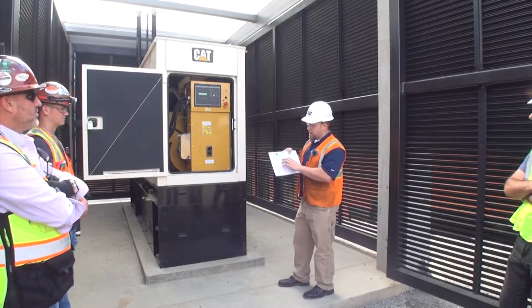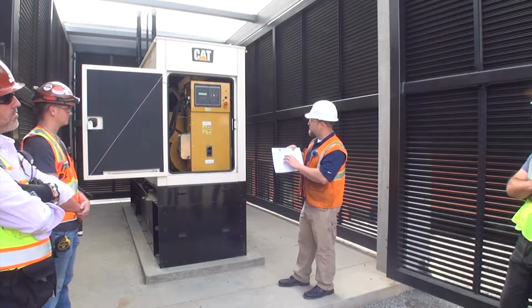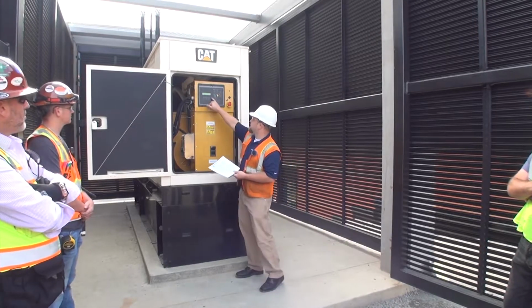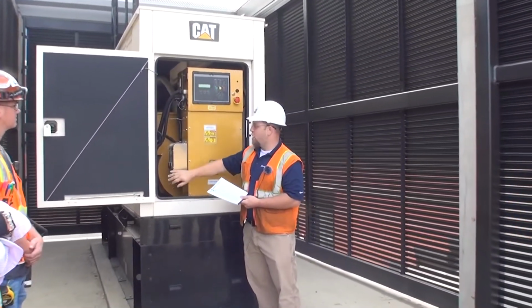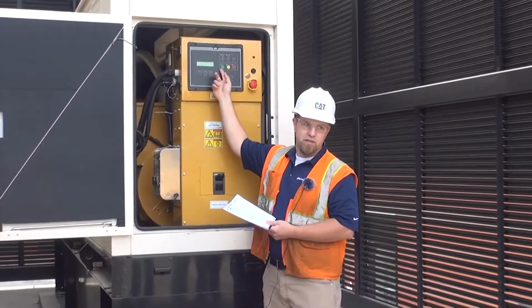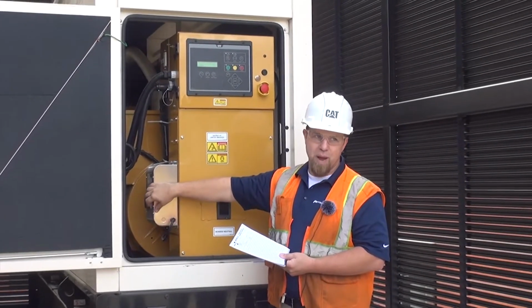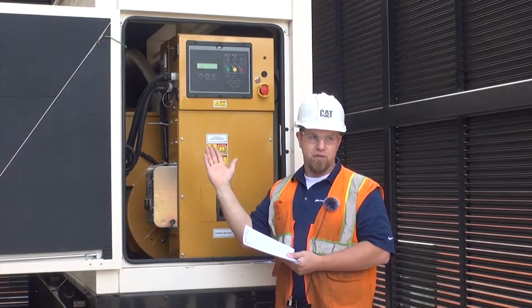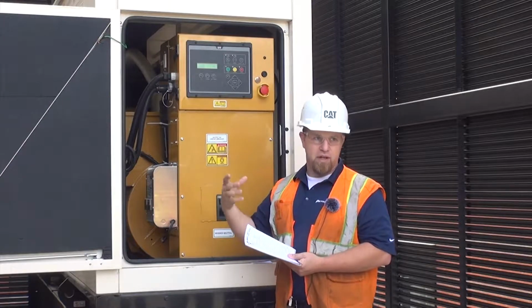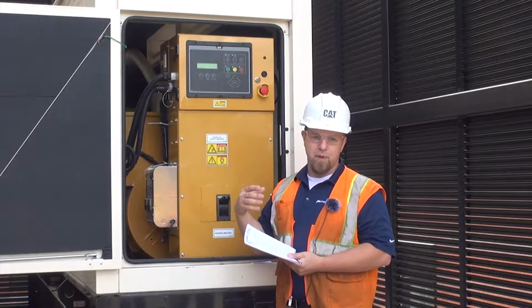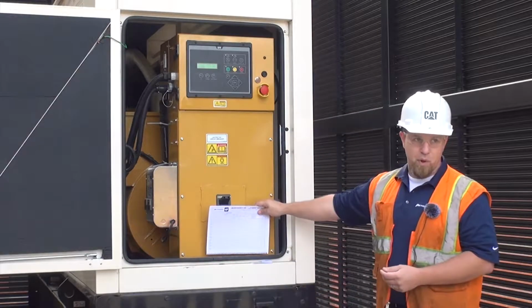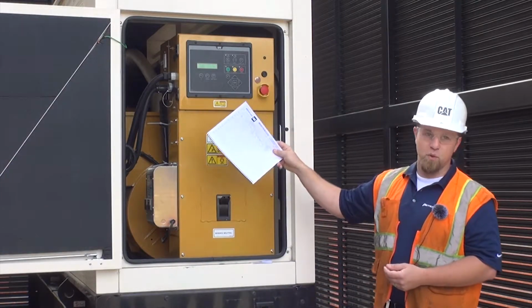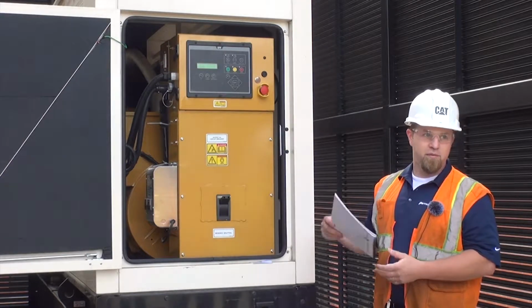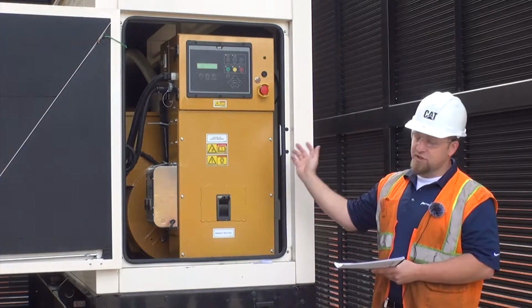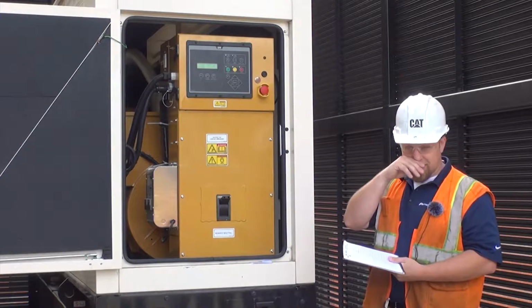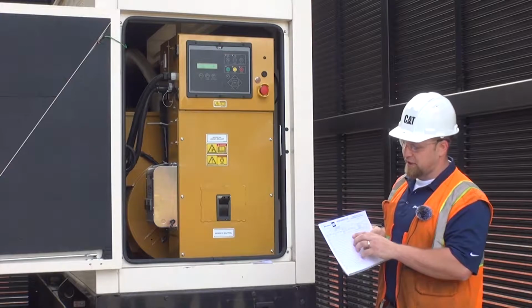Battery charger, that's part of one of your checks, and you can do it two different ways. You'll see 13.5 volts here. I always recommend not getting used to just trusting this panel, but walking around to check the actual battery charger, where you'll see the amps needle just a little off zero. Good rule of thumb to not be pencil whipping, because it's easy to leave this book in here, come out, open the door, pencil whip it, put it back, and walk away. If you get used to doing your weeklies actually walking around and checking these things, you'll be way better off and catch problems before they fail.